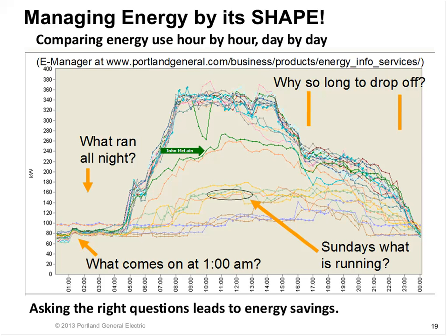And it's a great way to ask questions without knowing a lot of the technicalities if you're measuring kilowatt hours. In this case, the kW on the left. So one of the questions the school had was, why so long to drop off? Why, if people are gone, is this still a lot of energy use? And in fact, they found out it was the janitorial service that came in every night.